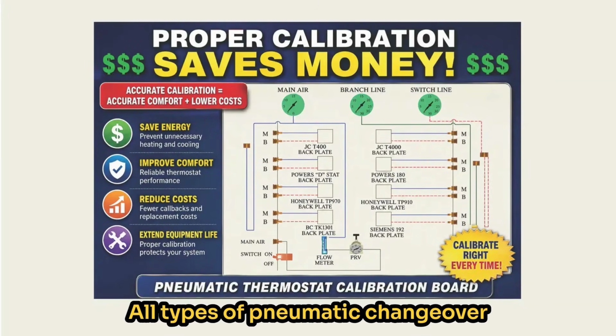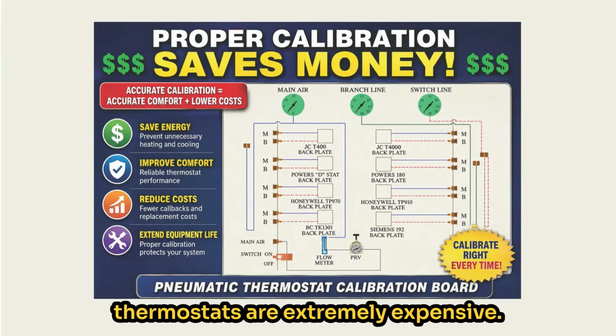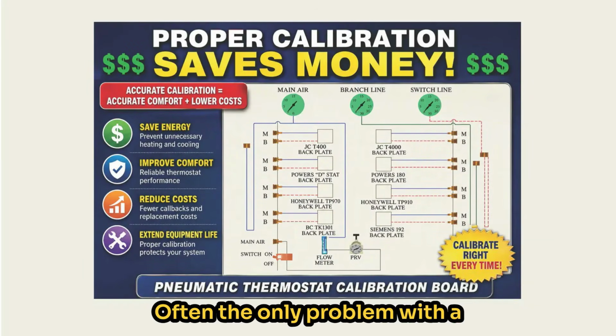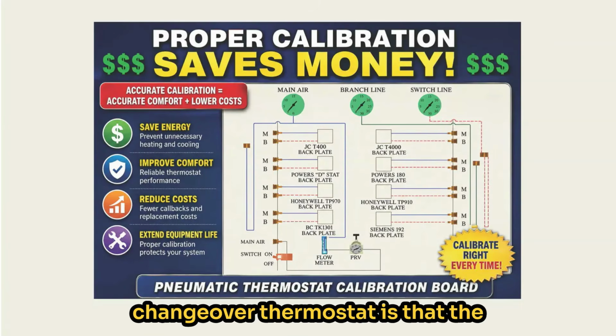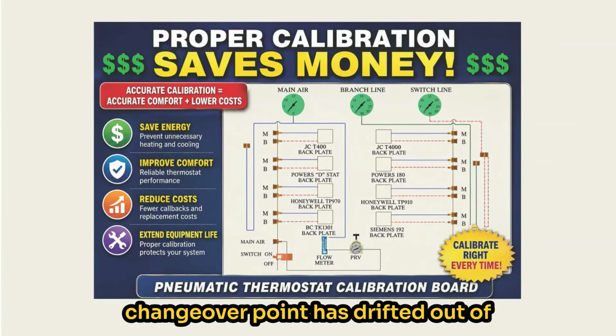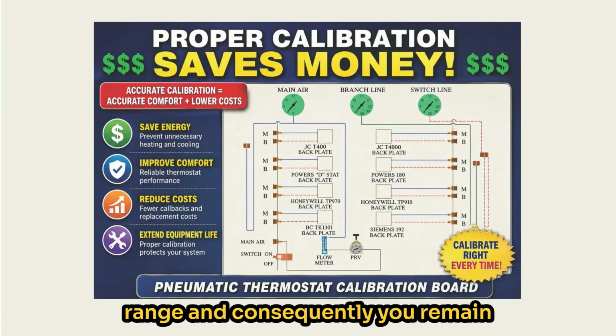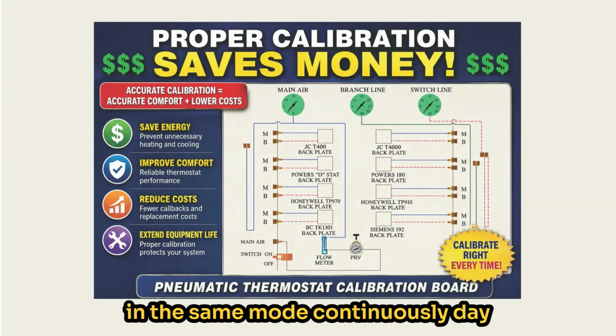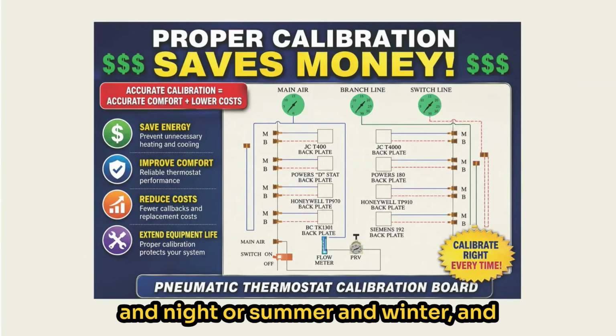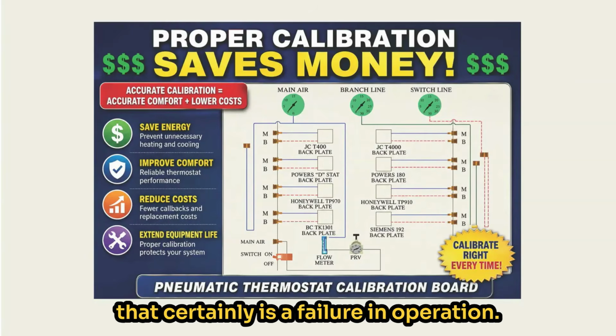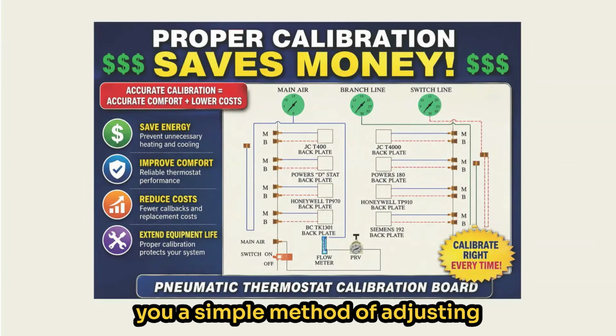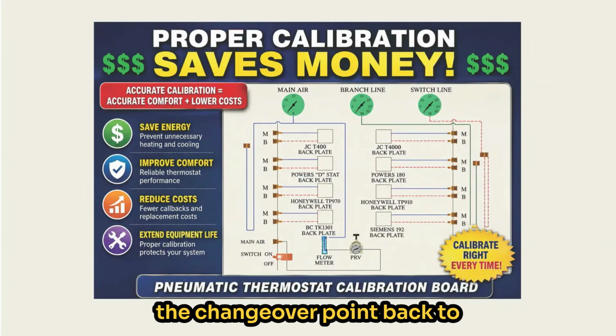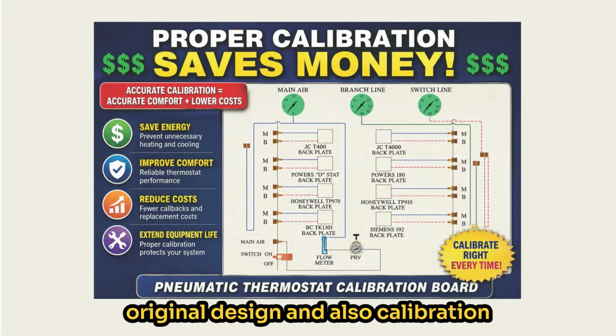All types of pneumatic changeover thermostats are extremely expensive. Often the only problem with the changeover thermostat is that the changeover point has drifted out of range, and consequently you remain in the same mode continuously, day and night or summer and winter, and that certainly is a failure in operation.